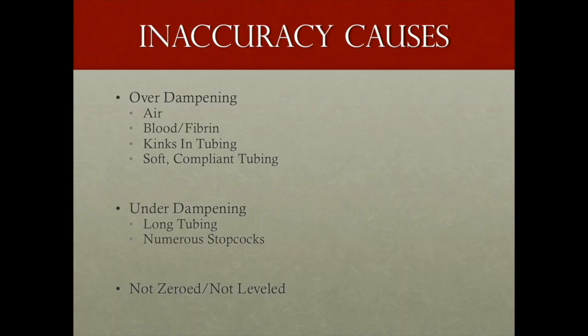So what causes overdampening or underdampening? Overdampening can be caused by air bubbles within the tube system, which can be troubleshot by flushing them out. Blood or fibrin can also cause it, and again these can be flushed out or the tubing can be exchanged. Kinks in the tubing will also cause dampening, as will using the wrong type of tubing.